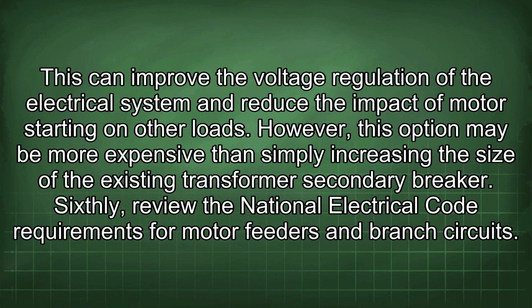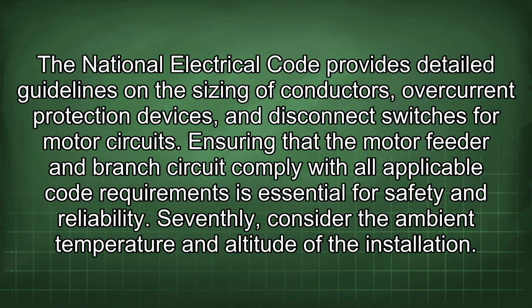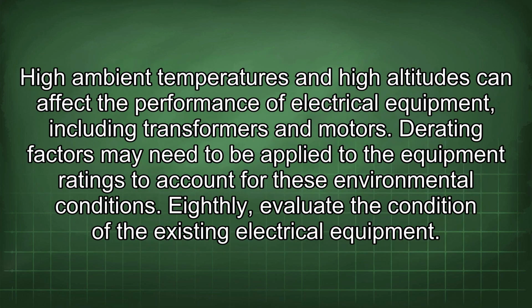Sixthly, review the National Electrical Code requirements for motor feeders and branch circuits. The National Electrical Code provides detailed guidelines on the sizing of conductors, overcurrent protection devices, and disconnect switches for motor circuits. Ensuring that the motor feeder and branch circuit comply with all applicable code requirements is essential for safety and reliability. Seventhly, consider the ambient temperature and altitude of the installation. High ambient temperatures and high altitudes can affect the performance of electrical equipment, including transformers and motors. Derating factors may need to be applied to the equipment ratings to account for these environmental conditions.